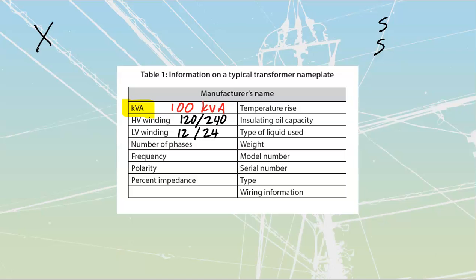There are two other H's and X's that we need to talk about. They don't lay them out inside of here, so you're going to have to make that note. XO and HO are going to be your identifications for any neutral point. If you're doing a 120/240 transformer or something like that, you can connect an HO to a high voltage neutral, and you would connect an XO to a low voltage neutral.